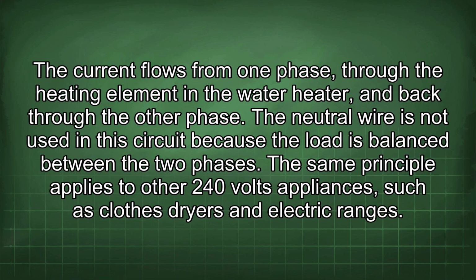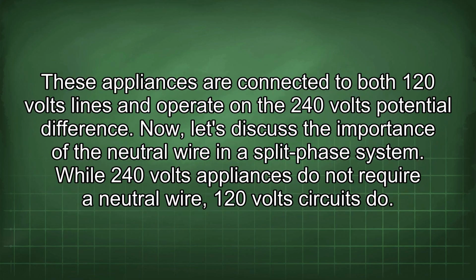The current flows from one phase through the heating element in the water heater and back through the other phase. The neutral wire is not used in this circuit because the load is balanced between the two phases. The same principle applies to other 240 volt appliances such as clothes dryers and electric ranges. These appliances are connected to both 120 volt lines and operate on the 240 volt potential difference.